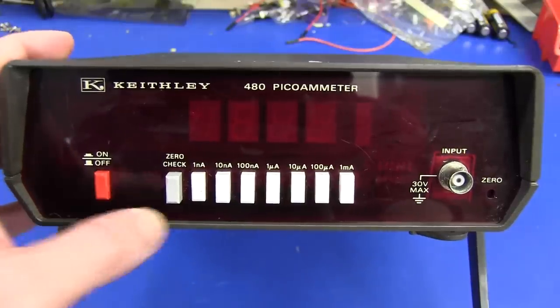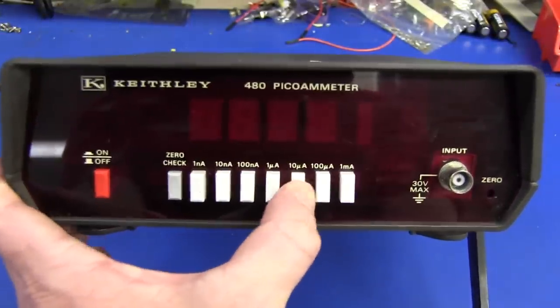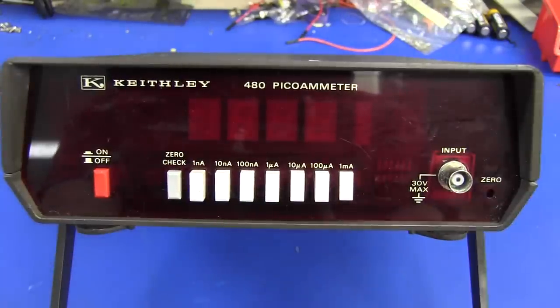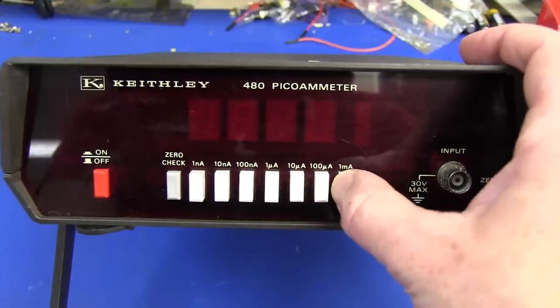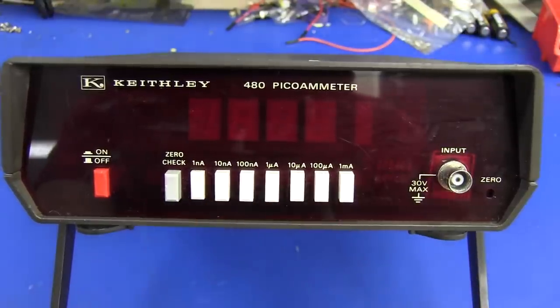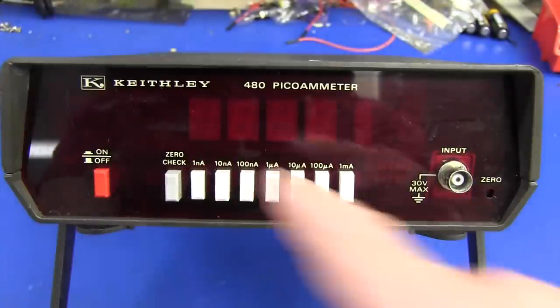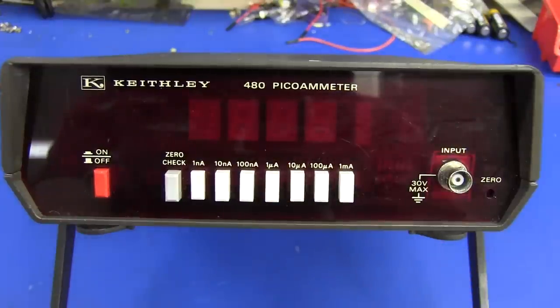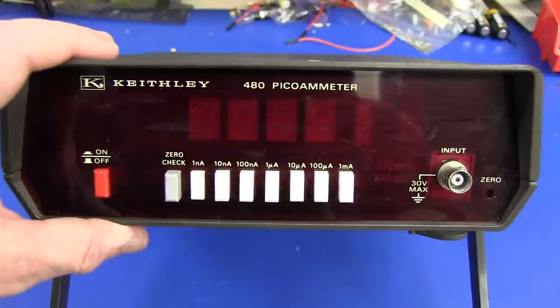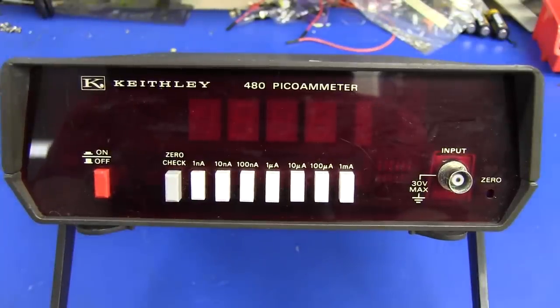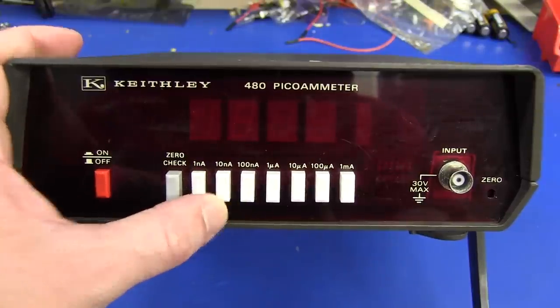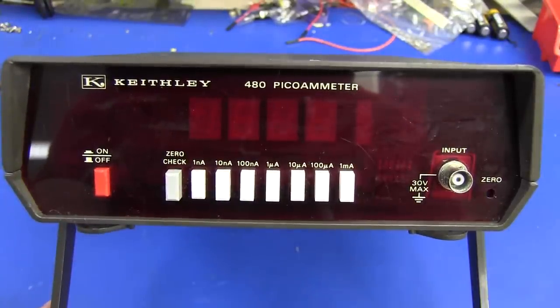It's very old school. It's got the old-fashioned ganged push button range switches here, and it's very simple. It's got a single BNC input. It's got a zero adjust pot down here on the front panel, which is really nice, and it has ranges from 1 milliamp full scale all the way down to 1 nanoamp full scale. So with a 3.5-digit display, as you can see behind the red perspex there, it has a resolution of about 1 picoamp, which is really quite nice. Very handy unit for measuring low currents. And it is a feedback operational type, so the burden voltage on this thing is incredibly low. This one's spec'd to about 250 microvolts burden voltage.